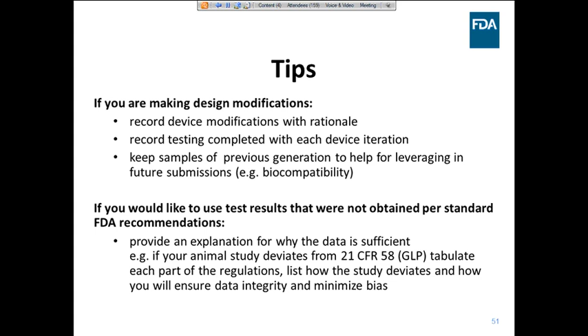similar manufacturing processes. If you would like to use test results that were not obtained per standard FDA recommendation, we strongly suggest that you provide an explanation for why the data is sufficient. So for example, if your animal study deviates from GLP requirements, you should tabulate each part of the regulation, list how the study deviates, and how you will still be able to ensure the integrity of the data and minimize bias.